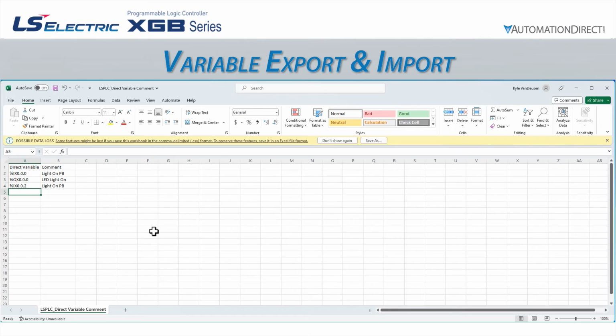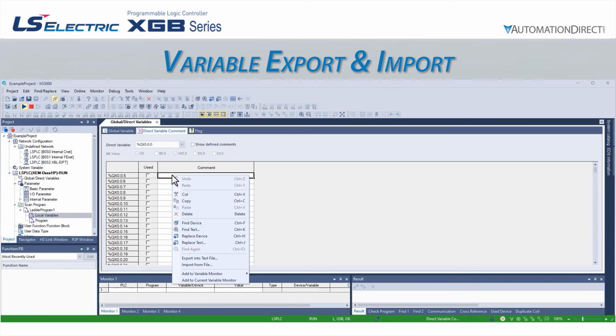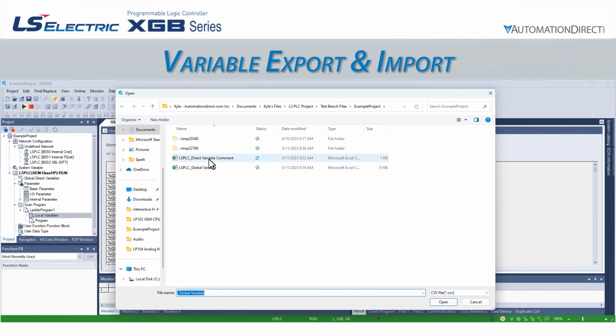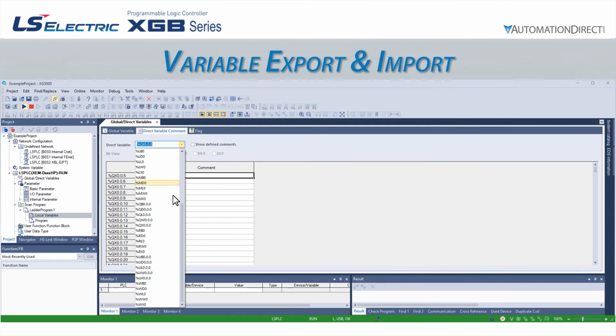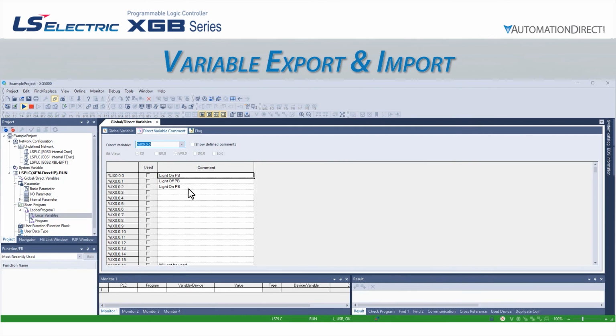Variable functionality also factors in. If, for example, we have a 16-input CPU, there is no point in commenting on direct variable address %ix0.0.16 or higher. Only %ix0.0.0 to .15 will ever be tied to an actual CPU point, since the %ix0.0.xxx range is reserved for CPU inputs only. The comments will be included in the program, but will only serve to confuse the programmer on which variables are being used.